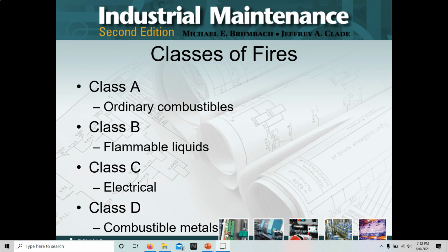They also have cooking grills. All of those cooking oils, while they're a flammable liquid, have some unique characteristics, and where they're being used has its own unique problems. So they've come up with an extinguisher just for them. It's the Class K extinguisher, or the Class K fire. Any fire that you find in a commercial kitchen type environment is going to be classified as a Class K fire, which is nice because K is for kitchen.